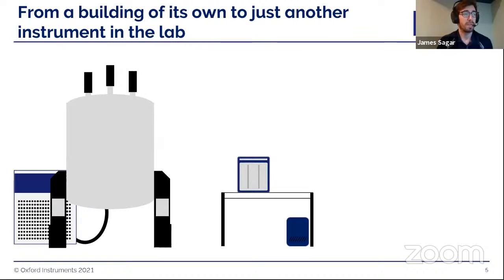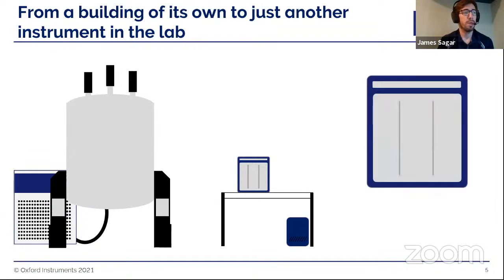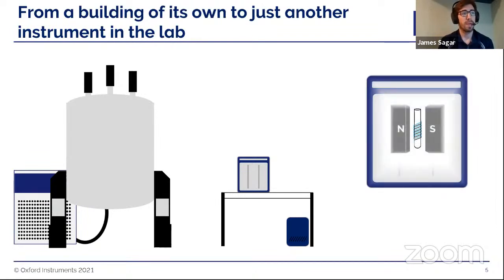We take the same design philosophy for our instrument, the X-Pulse, as a high field instrument, separating our magnet and our electronics console. In our magnet, we have a large permanent magnetic field, about 1.47 Tesla. What that means is that you can just drop your sample straight into the top of the instrument on the bench next to you while you're doing your chemistry.